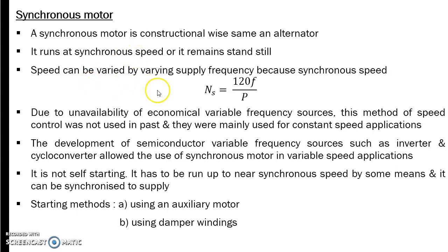Speed can be varied by varying the supply frequency, because synchronous speed is given by 120 F by P. So V by F control that we studied in your induction motors can be applied to the synchronous motor also. You can apply the V by F control.